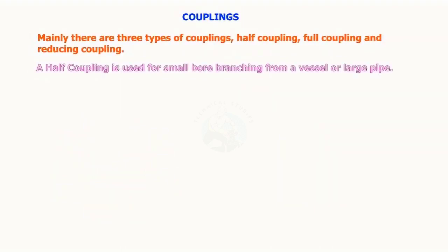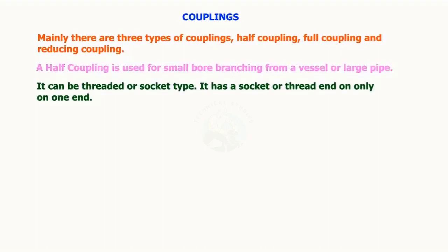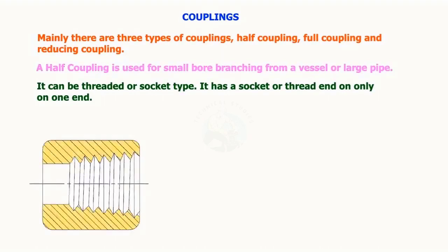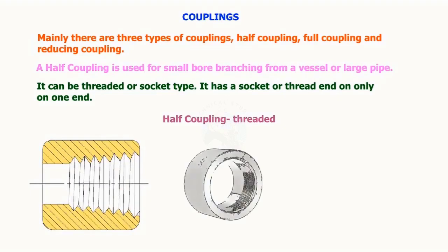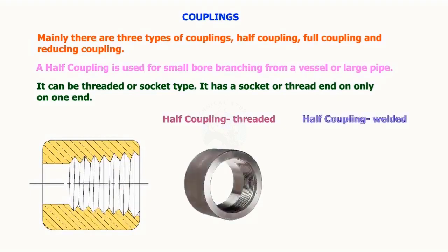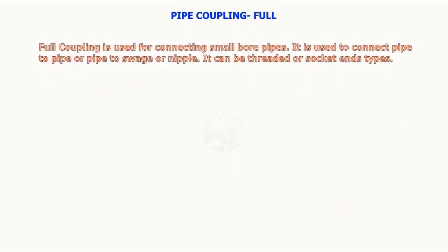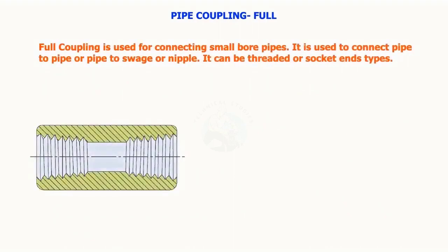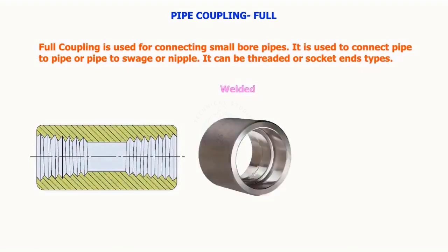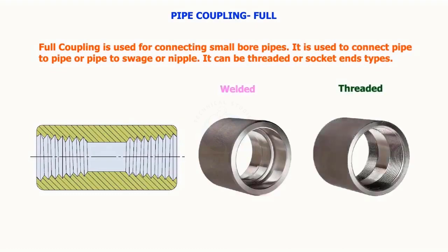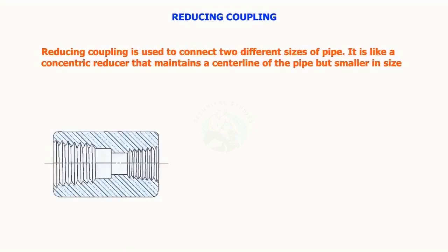Mainly there are three types of couplings: half coupling, full coupling, and reducing coupling. A half coupling is used for small bore branching from a vessel or a large pipe; it can be threaded or socket type, with a socket or thread end only on one end. Full coupling is used for connecting small bore pipes — to connect pipe to pipe, or pipe to swage or nipple — and can be threaded or socket end types. Reducing coupling is used to connect two different sizes of pipes; it is like a concentric reducer that maintains the center line of the pipe but is smaller in size.